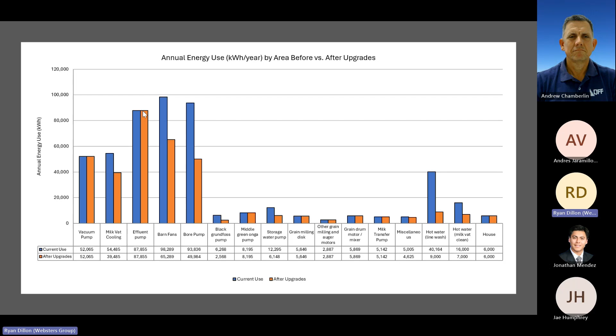A few other small savings there towards the right-hand side, 3 from the right-hand side. We've got the hot water in the line wash. Now that's close to an 80% reduction, because that hot water system previously had an electric element. When you have a heat exchange unit that's connected in line with the refrigeration system, the refrigerant travels through and uses that effectively as a condenser. It's almost free energy, so significant reduction in hot water use, as well as the hot water system for the milk vat clean, which is to the right there, where you just install a heat pump hot water system, given it's up to 80% more efficient than a standard residential system, which was what was currently being used. So significant energy savings across all equipment types.